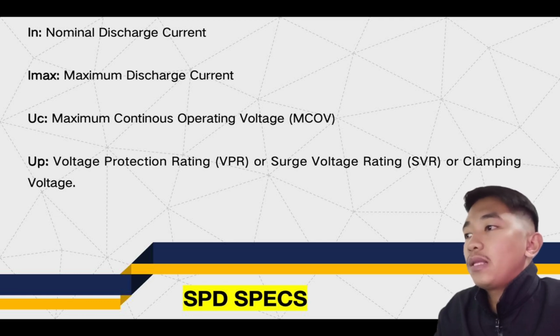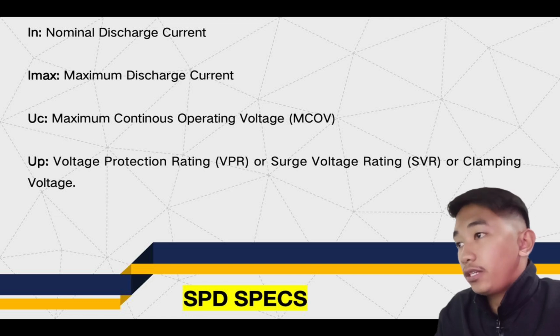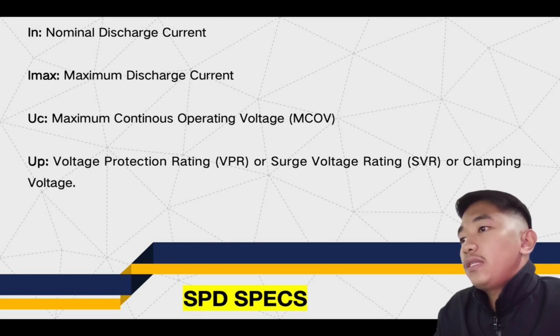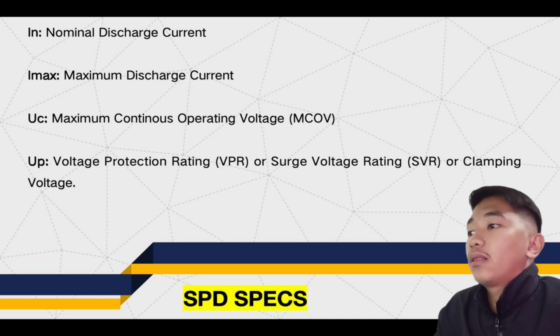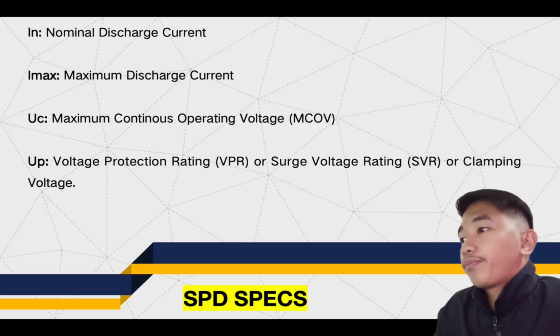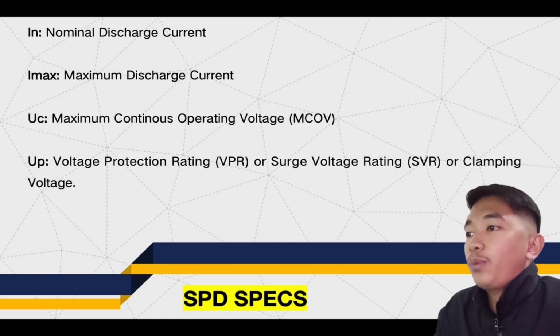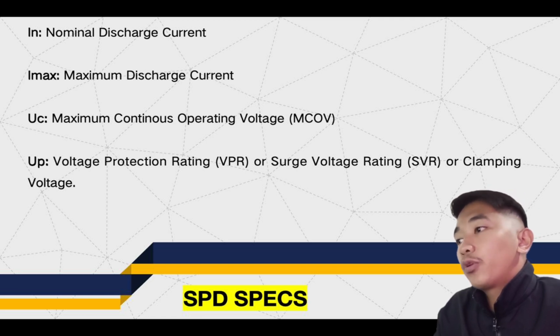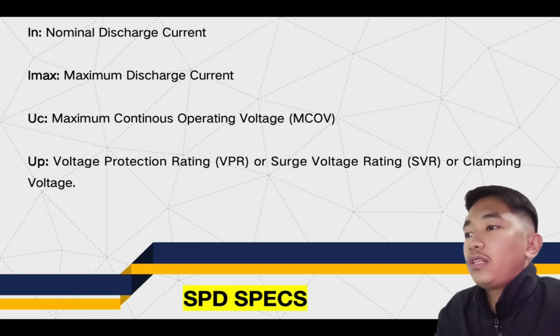This rating indicates the maximum voltage that can be applied to the SPD continuously during standard operation without affecting its performance. Last is the voltage protection rating, VPR, also known as U sub P, a key specification for a surge protection device. It indicates the maximum voltage that the SPD will allow to pass through to the protected equipment during a surge event. Essentially, it shows the clamping voltage, the voltage at which the SPD will begin to conduct and divert the surge energy to the ground, protecting the connected equipment from the high voltage spikes.